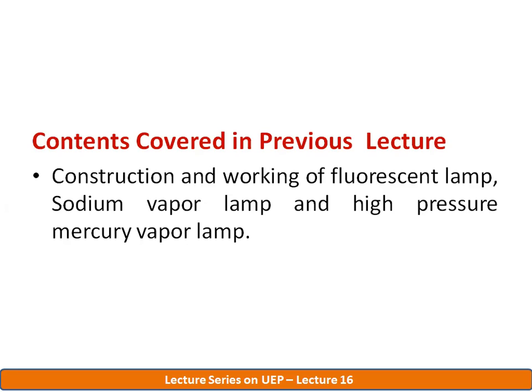Its working principle we already studied, and the efficiency of the lamp is about 40 lumens per watt, and working life is about 7500 hours. 5000 hours is the normal life. After 4000 or 5000 hours, the light emitted from the lamp reduces by 15%.